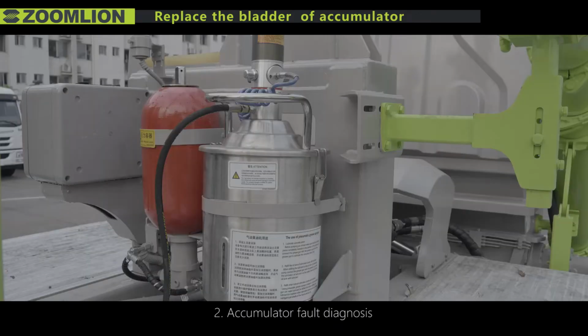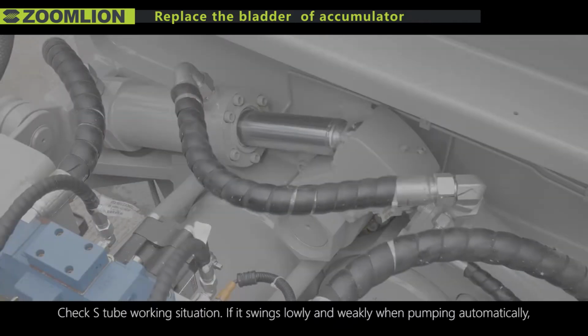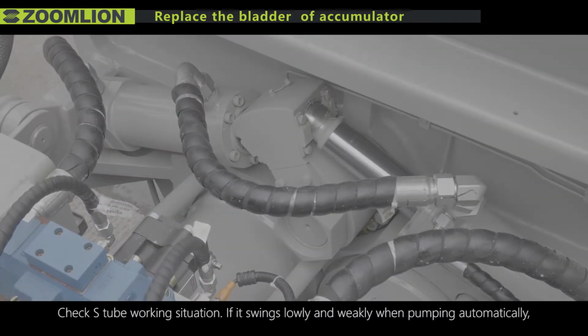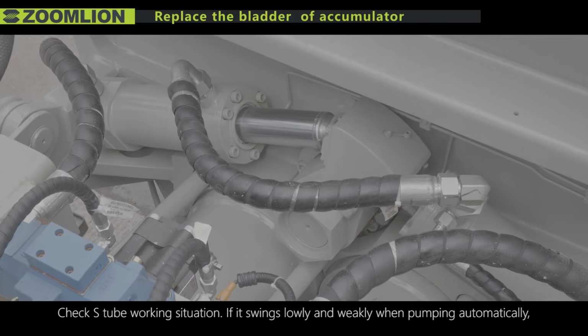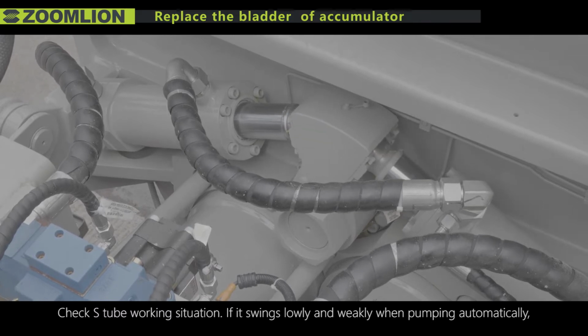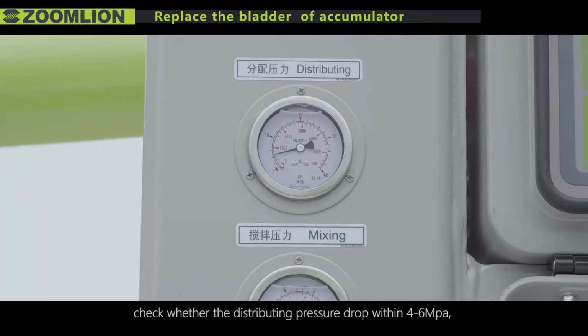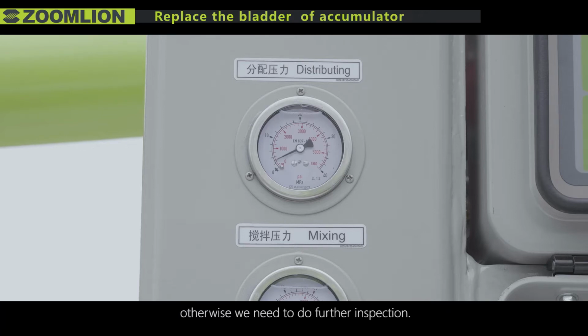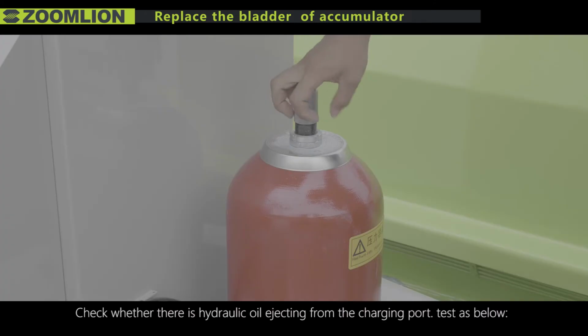Second, accumulator fault diagnosis. Check S-tube working situation. If it swings slowly and weakly during pumping automatically, check whether the distributing pressure dropped within 4 to 6 MPa. Otherwise, we need to do further inspection. Check whether there's hydraulic oil ejecting from the charging port. Test as below.